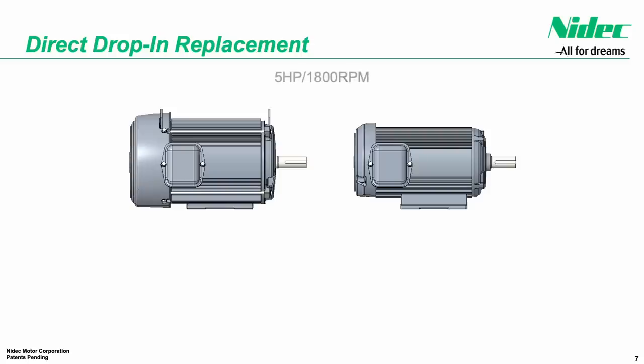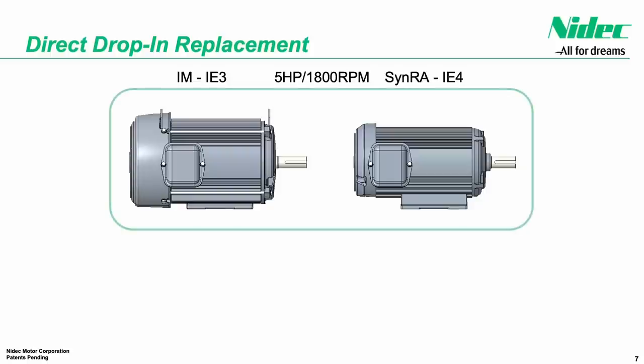Visually, we can see here how taking advantage of the improved power density allows a smaller motor design. In this five horsepower example, the standard induction motor design is in a 180 frame, and we have designed the SynRA mechanicals to match the same frame size, allowing easy drop-in replacement both mechanically and electrically if an end user will utilize an existing drive.